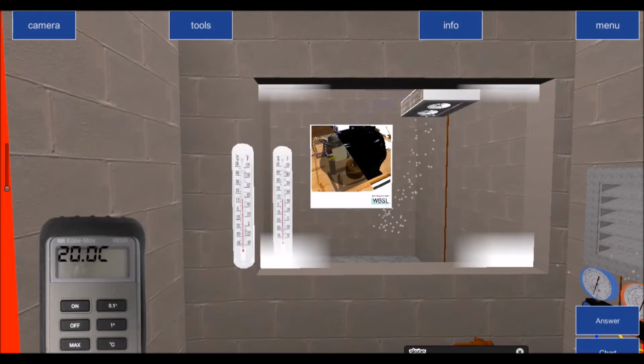The other thing that I need to say to you at this point in time as well, and it's in our notes as well, is that when it comes to a split air conditioning system for comfort cooling, the delta T total on the evaporator side is 15 to 20 degrees of a difference. So in other words, it's not unusual to have a room temperature or air on temperature of 18 degrees for comfort cooling, and an evaporating temperature of 5 degrees or even 7 degrees. So it can be anywhere between 15 to 20 degrees of a difference. That's how it works on a split system.